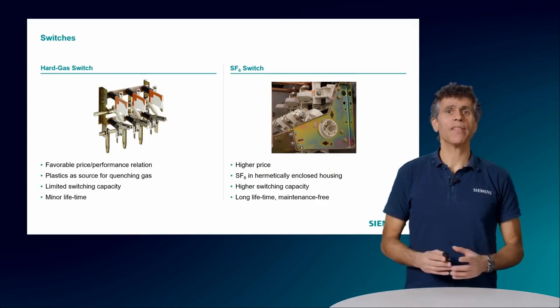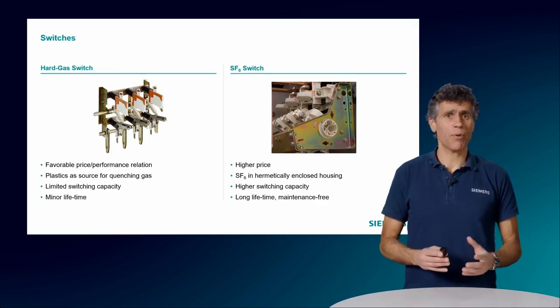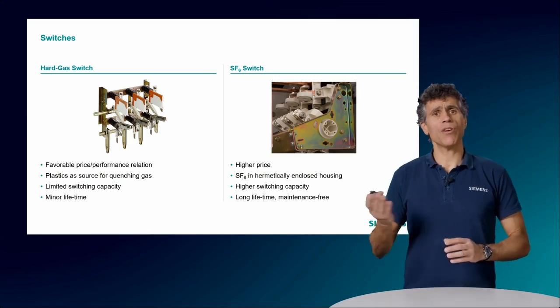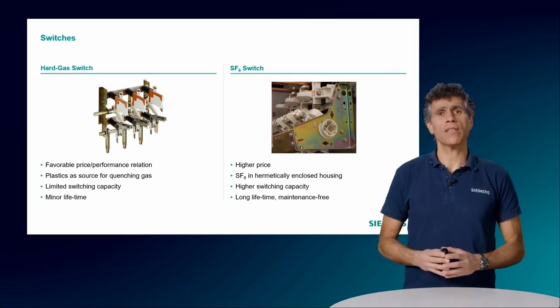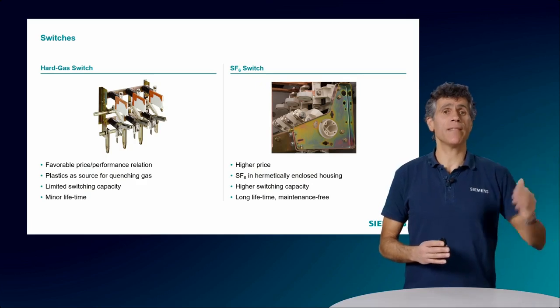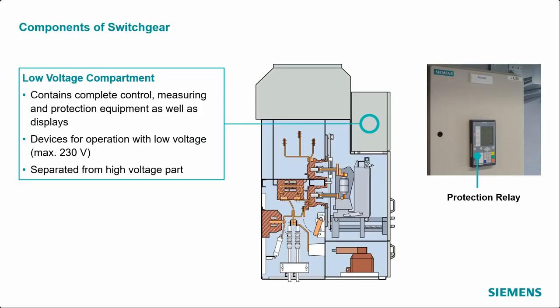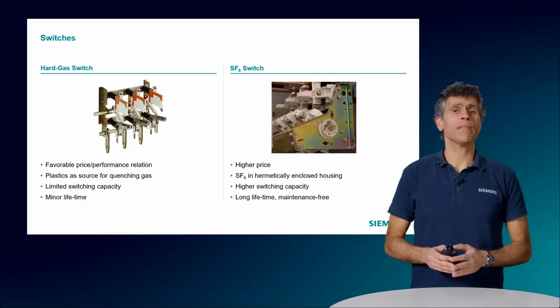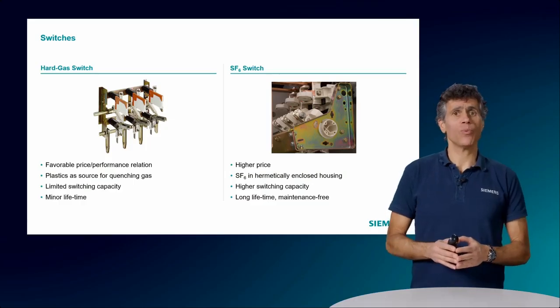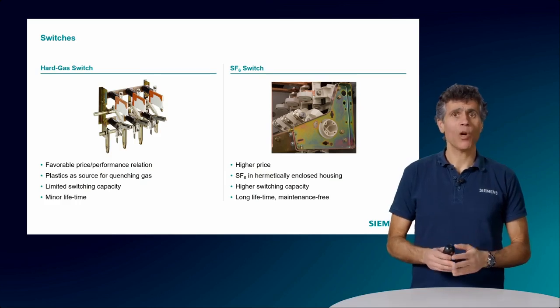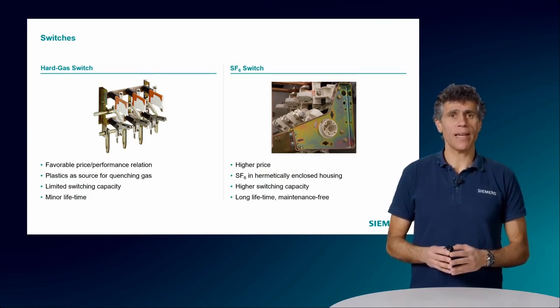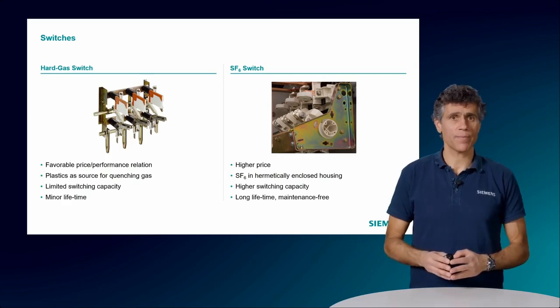A good comparison is your light switch at home. A switch does approximately the same. It simply switches on and off. If there is a short circuit, there is an upstream device that safely cuts the energy. So when would you select a switch instead of a circuit breaker? When a protective device for failure exists upstream, when it must be easy, cheap and small, when switching can be done manually. In sum, when there is no need for complex functioning and isolating the systems should be done quickly. A typical use is isolating a line or a transformer for maintenance purposes.